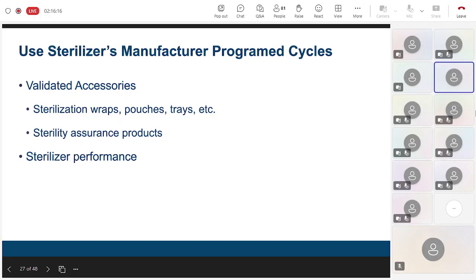Using validated sterilizer cycles also gives assurance of the sterilizer's performance. The sterilizer manufacturer would be able to provide a preventative maintenance plan and cycle performance confidence. And remember that though the sterilizer may have been validated and 510(k) cleared, the clearance may not include 3D printed medical devices. In fact, most sterilisation options available to sterile processing do not have clearance, requiring extensive sterilisation validation testing to be done. So that means that there are only very, very few, or one in actual fact, that can do this.